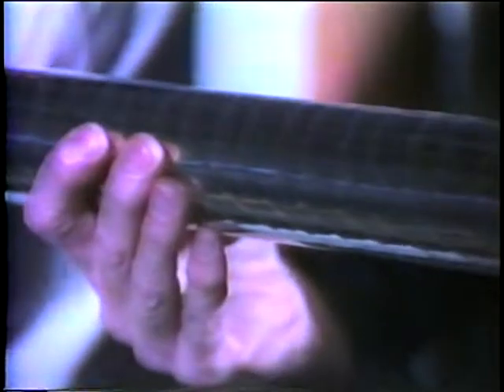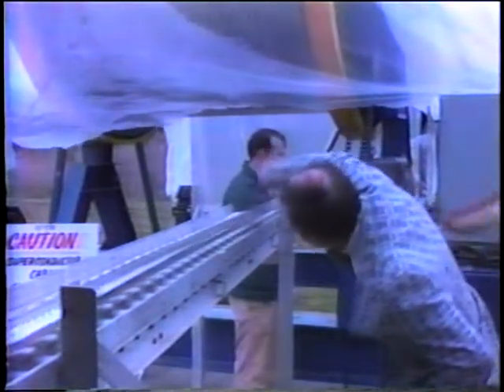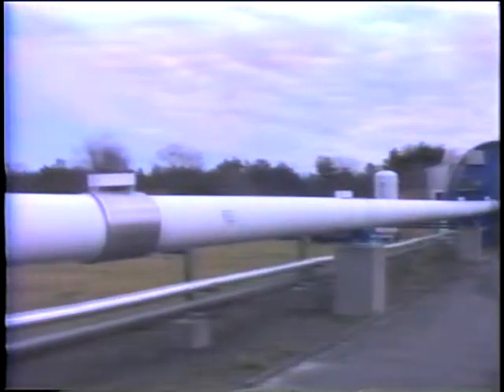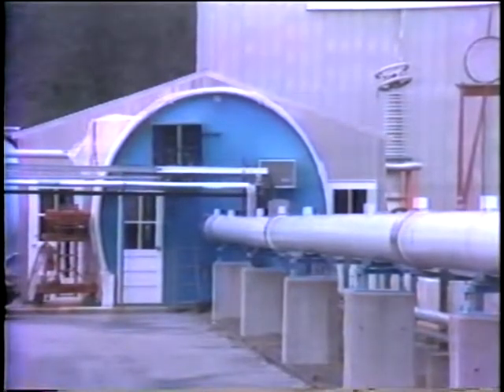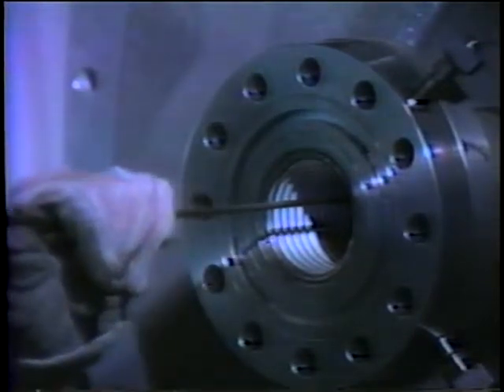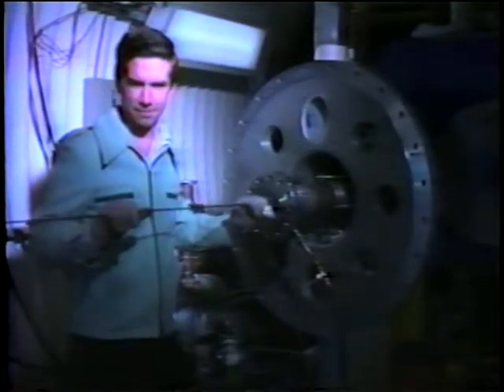With conventional cables, there is a heavy center conductor to take the strain of pulling the cable down the pipe. In the superconducting cable, all the components are relatively fragile, and stainless steel outer armor tapes were provided, which are welded to the pulling head to take the pull force of about 400 pounds. However, this was the first time such an operation had been tried, and there was a good deal of relief when the cable emerged at the far end of the pipe without suffering visible damage.